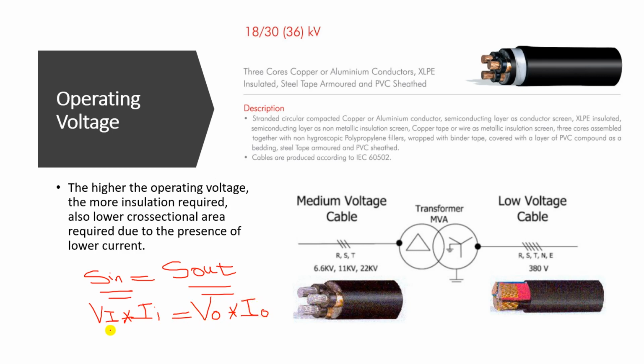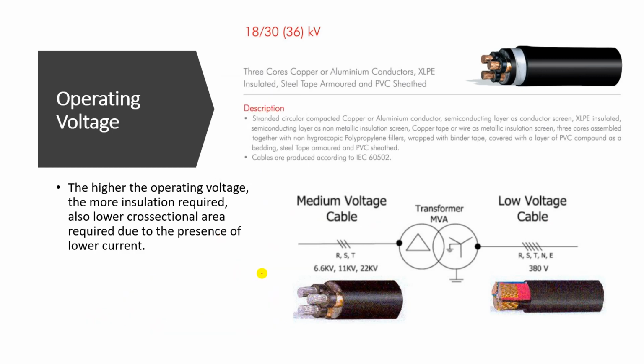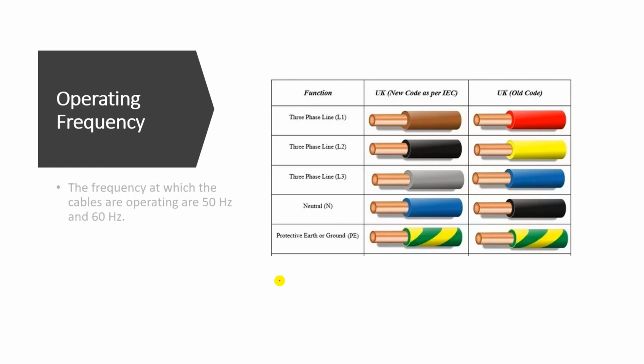As you can see, in the medium voltage the voltage is high, and in the low voltage it is low. So in order for this side to be equal to this side, the current should be low in the medium voltage and high at I out. This is a function of the transformer: increasing the voltage leads to decreasing the current, and decreasing the voltage leads to increasing the current. This is why the cross-sectional area and the insulation are different. The last thing is the operating frequency.